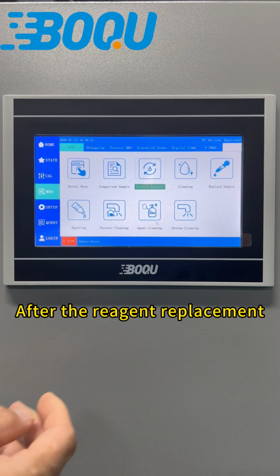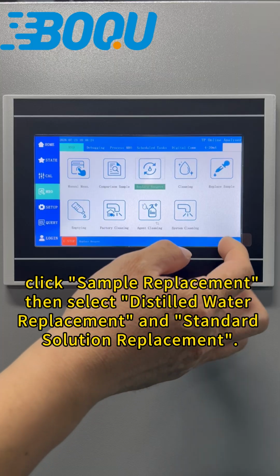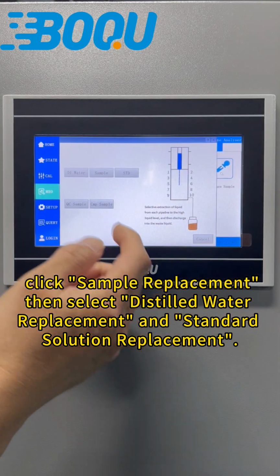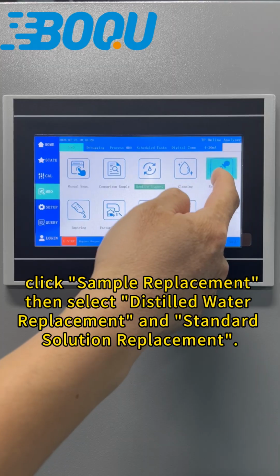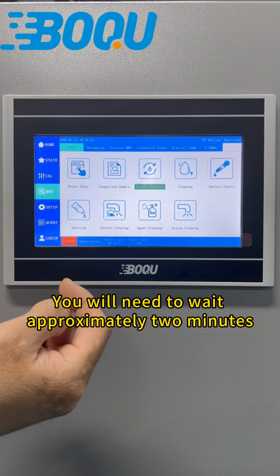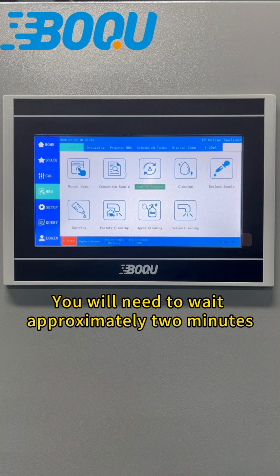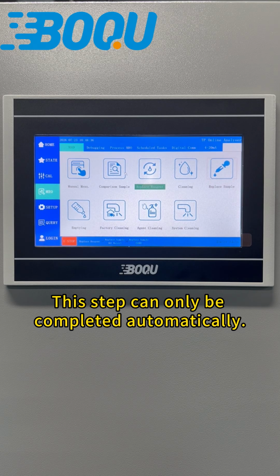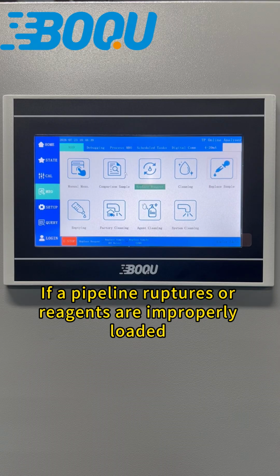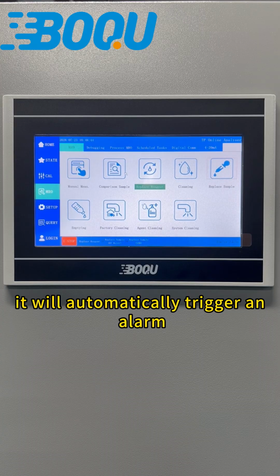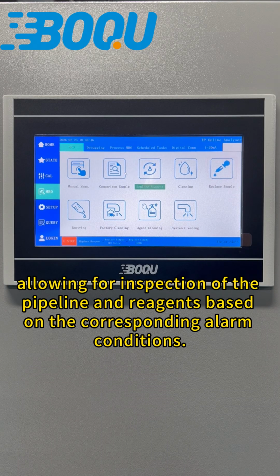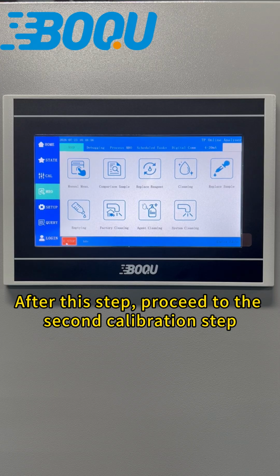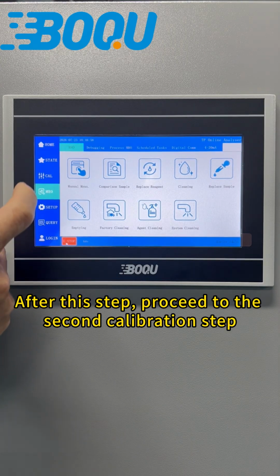After the reagent replacement, click Sample Replacement, then select Distilled Water Replacement and Standard Solution Replacement. You will need to wait approximately 2 minutes. This step can only be completed automatically. If a pipeline ruptures or reagents are improperly loaded, it will automatically trigger an alarm, allowing for inspection of the pipeline and reagents based on the corresponding alarm conditions. After this step, proceed to the second calibration step.